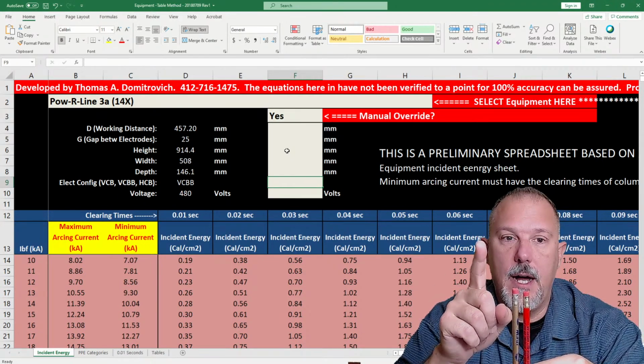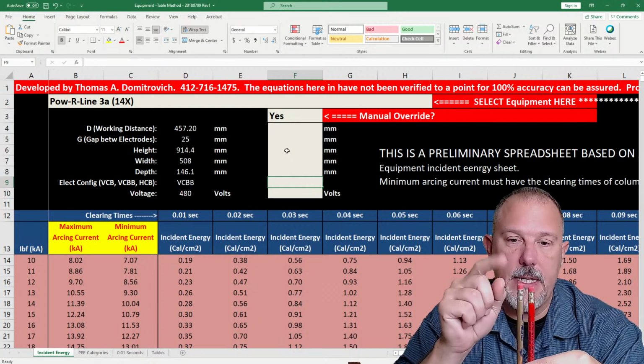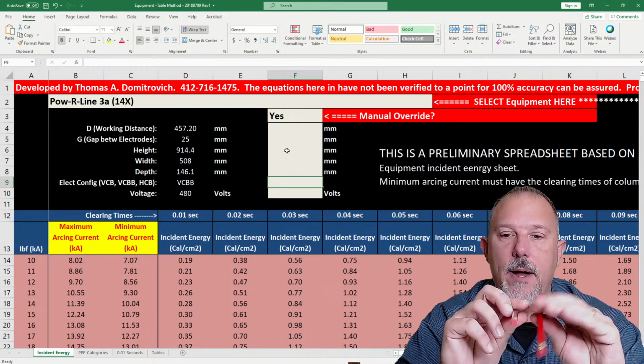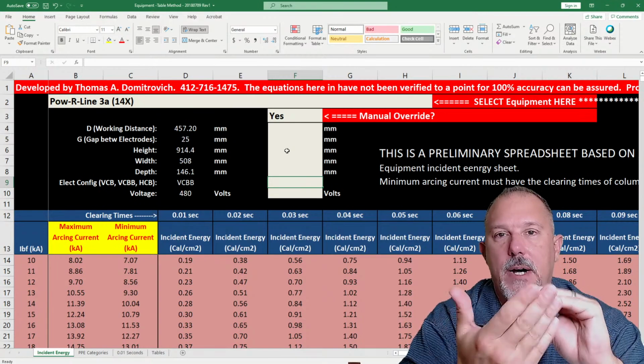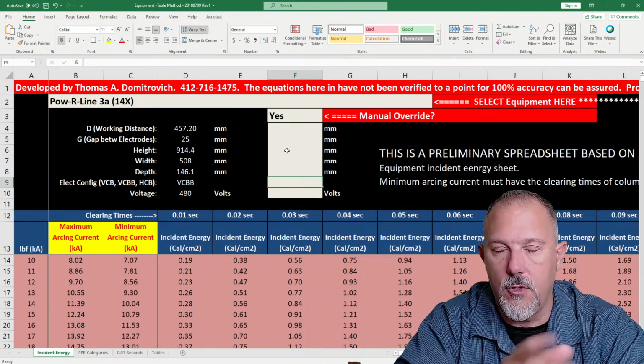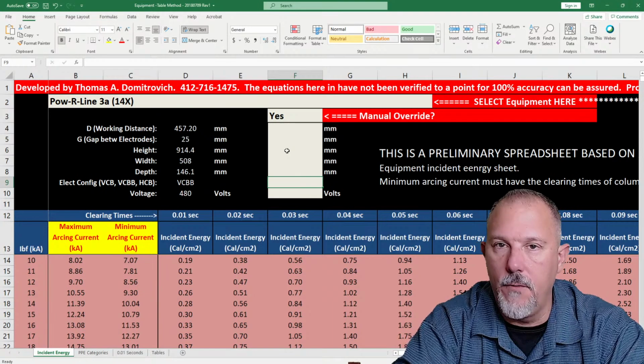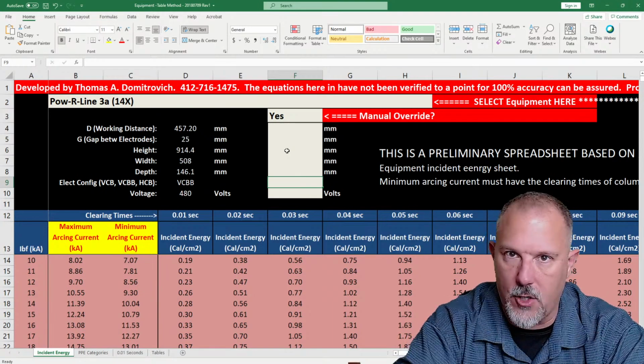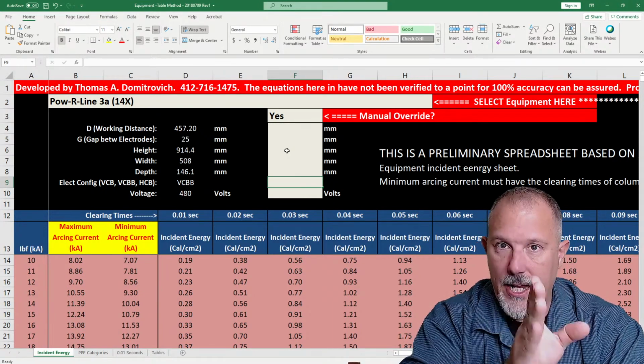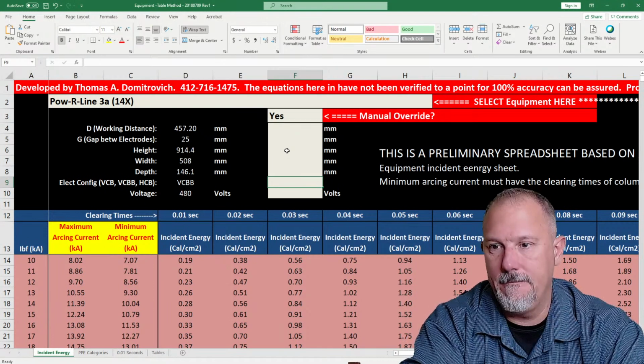If I have an HCB, which means now I'm looking at the end of the bus. Where would you see that? You might see it in a motor control center. You could see it in a low voltage assembly, depending upon where you enter the equipment. If you're looking at the end of a copper bus, that's the end.